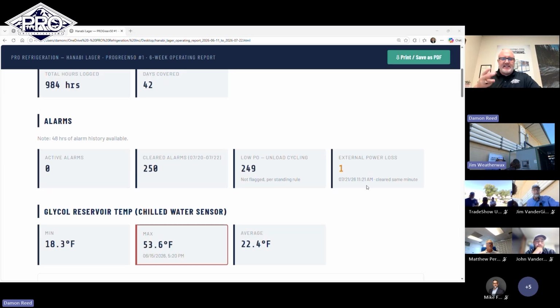Yeah, it cleared at the same time, so it might have been a brownout or something. But inside the control system, we monitor our control power. We have a battery backup that switches over for all the low voltage controls. If that loses power, it notifies and sends out an alarm. So it happened and it cleared within the same minute.